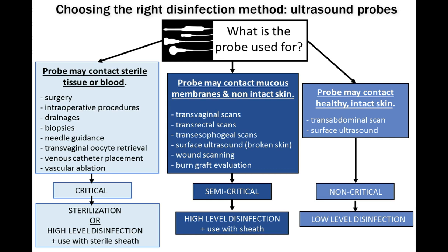So choosing the right disinfection method for your ultrasound probes requires that you decide what the probe is going to be used for. If the probe contacts sterile tissue or blood, such as in surgery and operative procedures, drainages, and so forth in this box, then it is considered critical and requires sterilization or high-level disinfection and the use of a sterile sheath. These are the present protocols that define what is required.